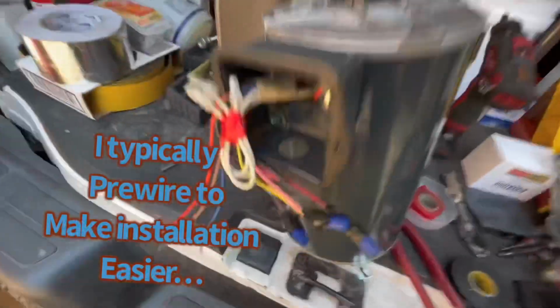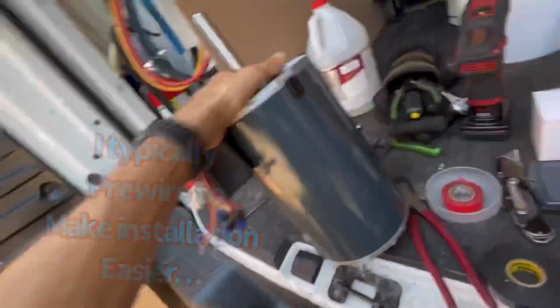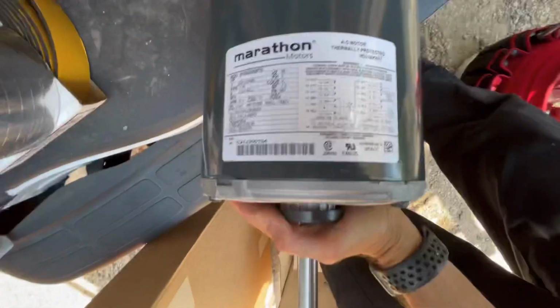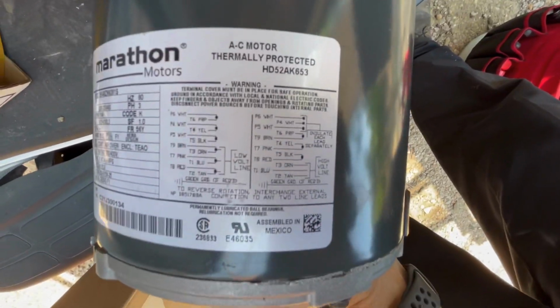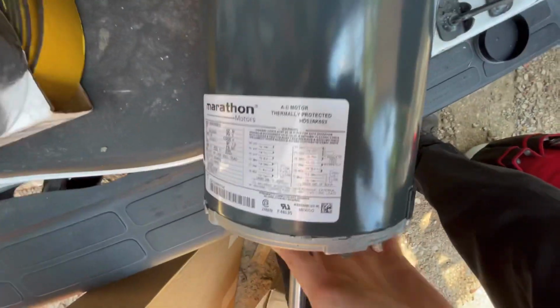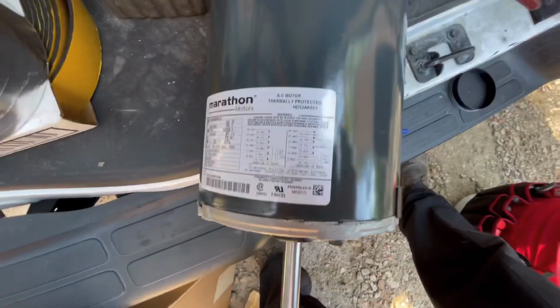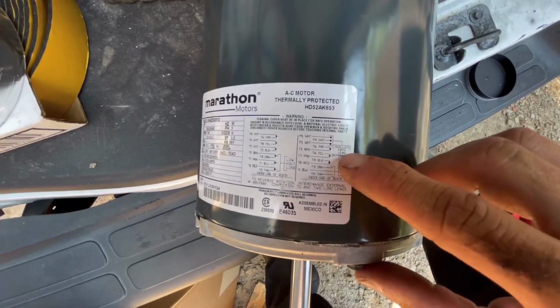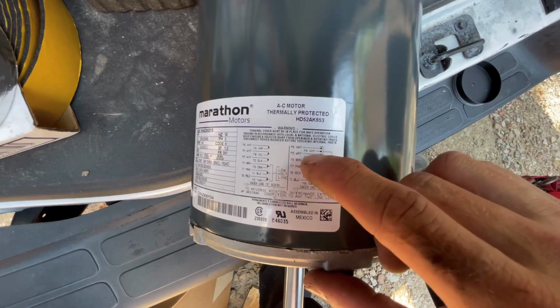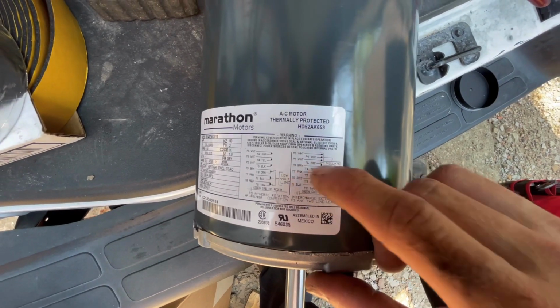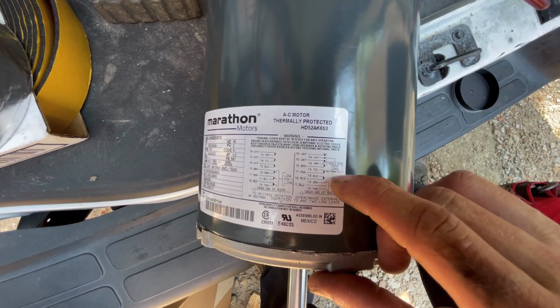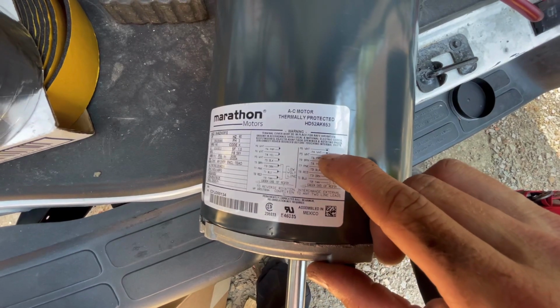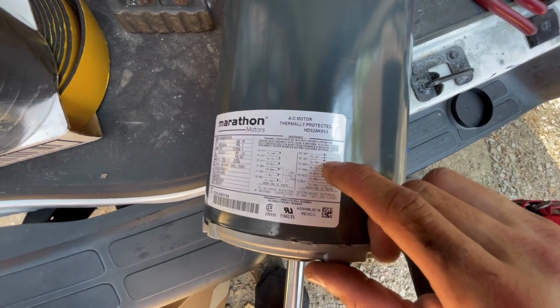Okay, I'm doing this in the back of my van because I don't have to do it inside the unit this time. Okay, so this is high voltage. Let me see if I can get this in the shot. It tells you exactly how to wire it. Set this here. Now one thing I just noticed, it's telling me for P6 white, P4 white, and P5 white, insulate each lead separately. That shows a wire nut, wire nut, wire nut. Okay, they're together, but they're separate.